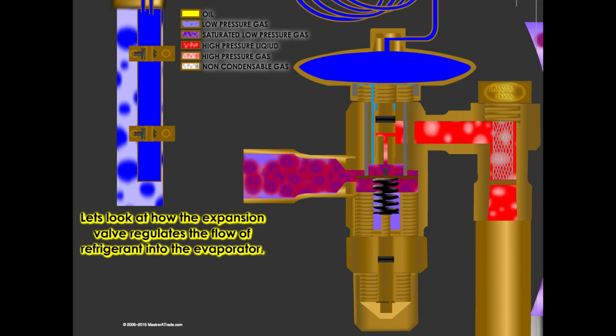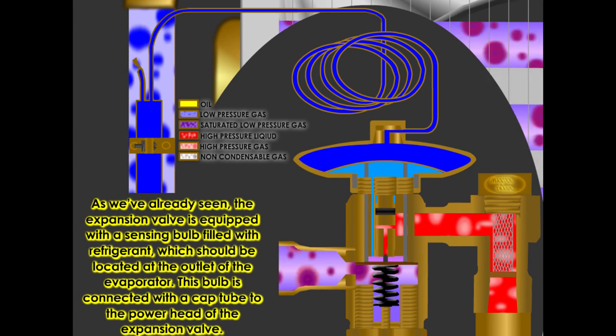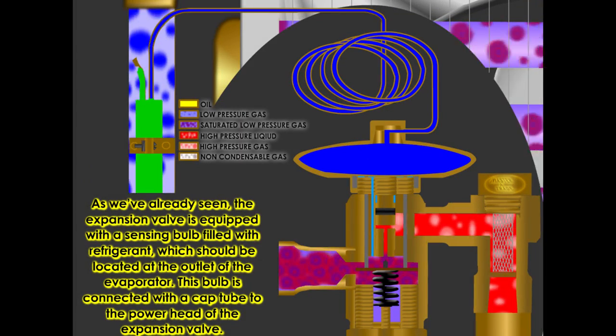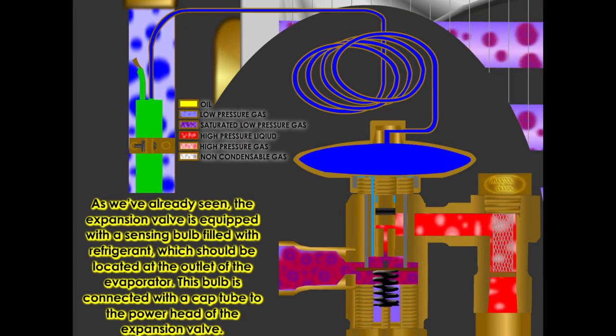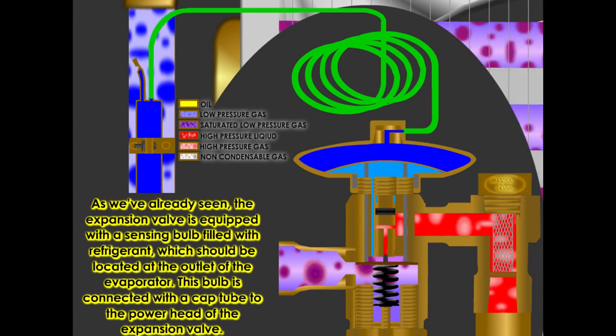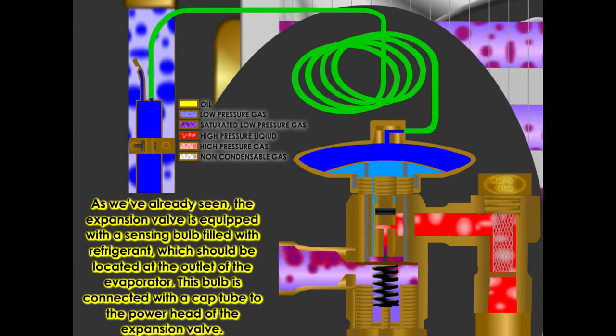Let's look at how the expansion valve regulates the flow of the refrigerant into the evaporator. As we've already seen, the expansion valve is equipped with a sensing bulb filled with refrigerant, which should be located at the outlet of the evaporator. This bulb is connected with a cap tube to the power head of the expansion valve.